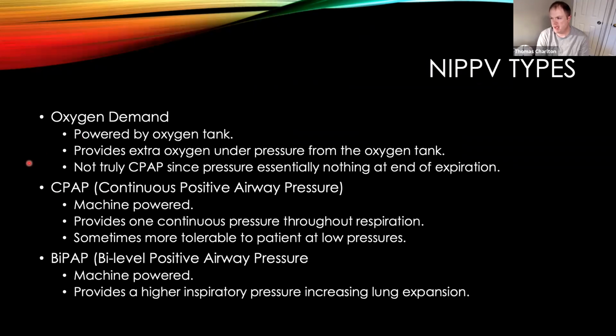The nice thing about CPAP is that it does provide a continuous pressure. So the motor within the CPAP machine is going to spool up and down, up and down, to maintain the same pressure throughout the entire course. If you inhale real sharply, it's going to provide extra flow to keep that pressure consistent. And when you begin to exhale, it's going to turn the pressure on that motor down a little bit. So that way, again, it maintains this continuous pressure across you.